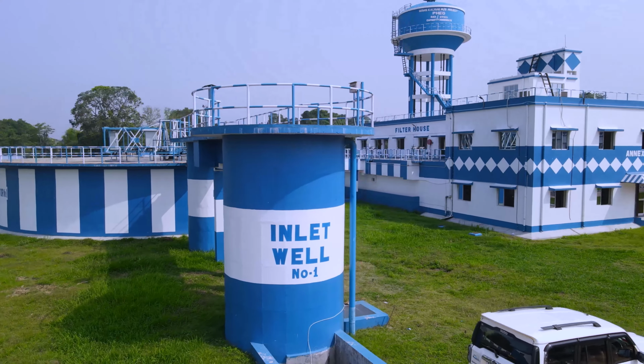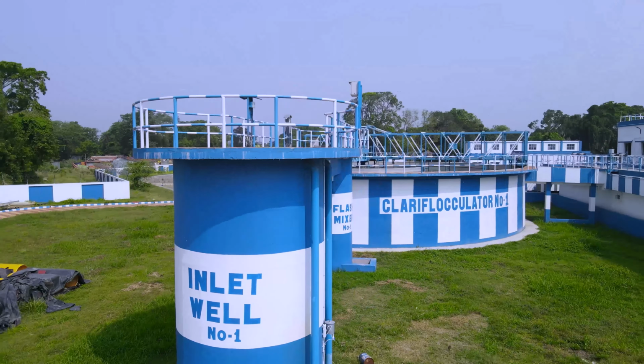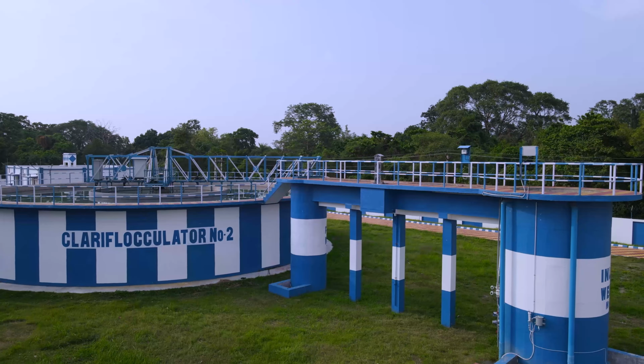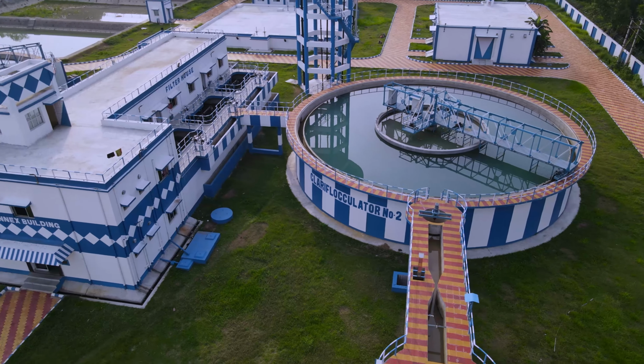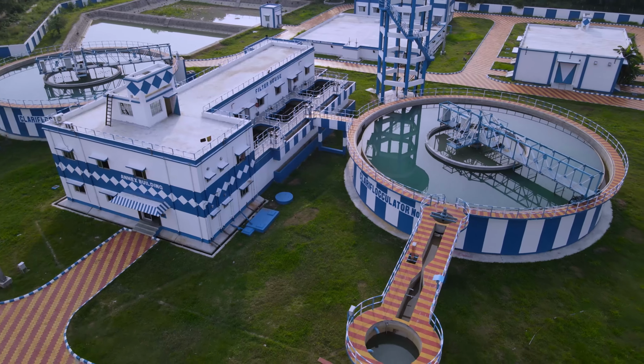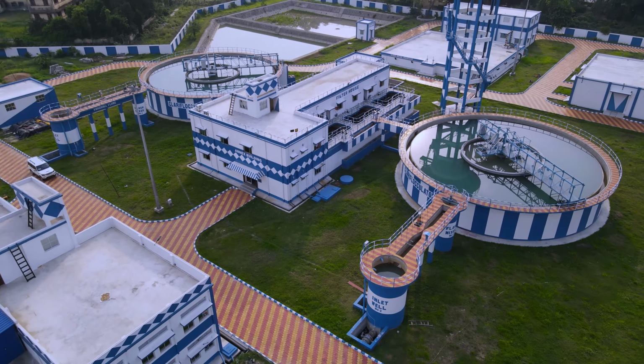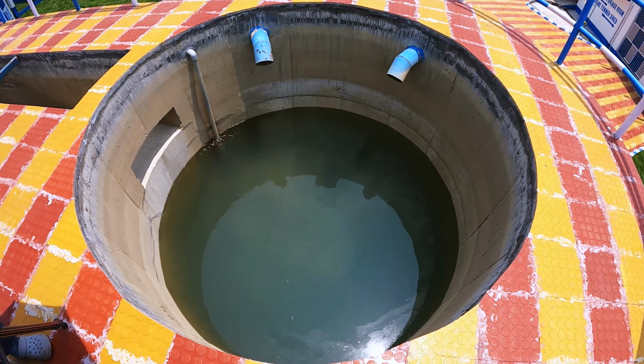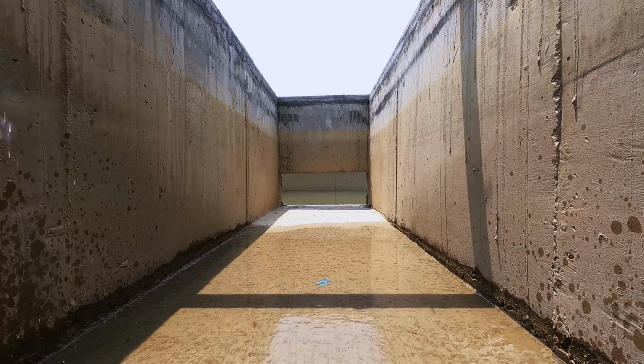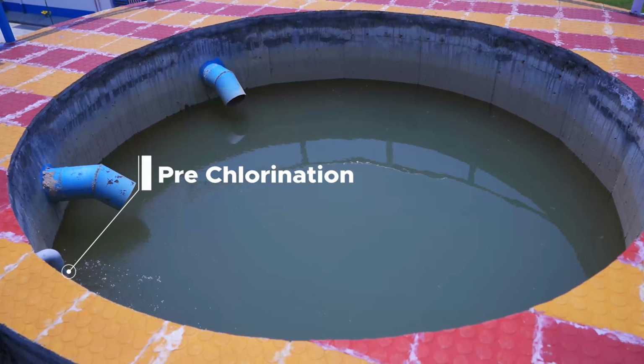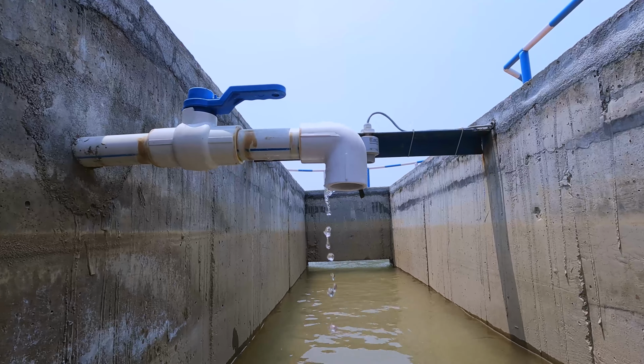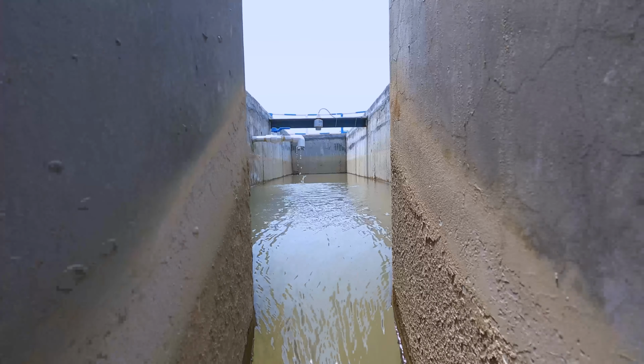Raw water enters into the processing plant through an underground pipe and then gets divided to enter simultaneously into both settling chambers, filling up the inlet well while flowing into the channel. First, pre-chlorination is done inside the inlet wells and then it flows through a Parshall flume, followed by alum dosing on raw water.